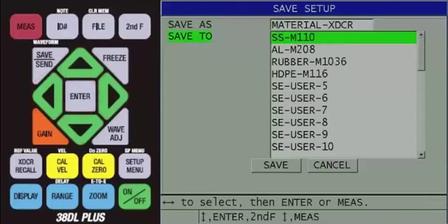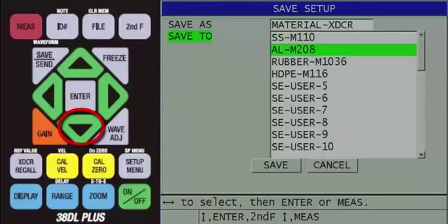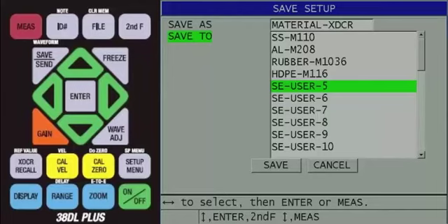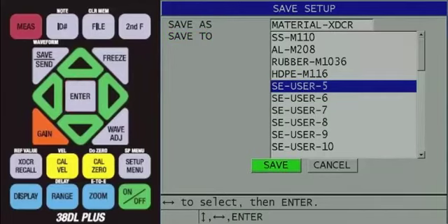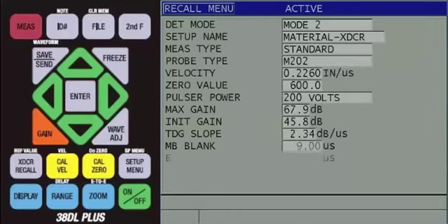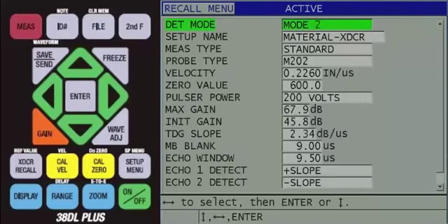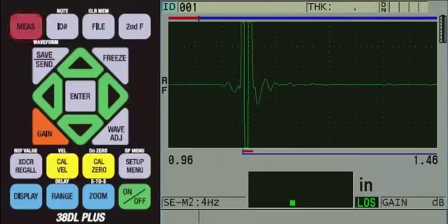key on the instrument. Now, the Save To line will be highlighted, and you can choose where to save the custom transducer setup. Use the arrow keys to highlight an available SE-user setup number. Then press the Enter key so Save is highlighted. Then press the Enter key again. The active screen showing all the setup parameters will now be displayed. From here, you can press the red Measure key to return to the measurement screen.